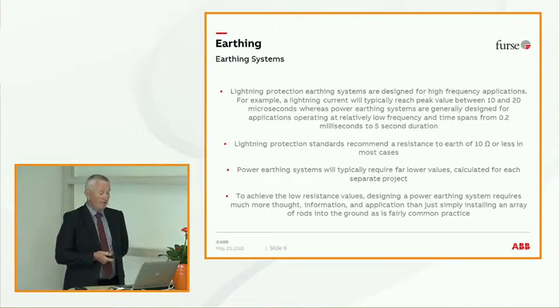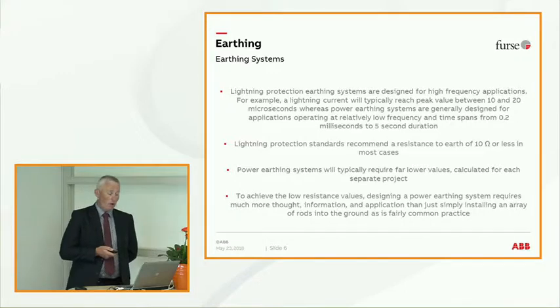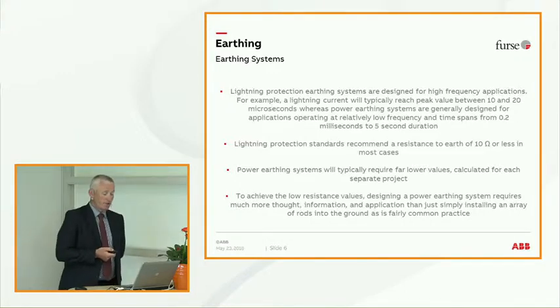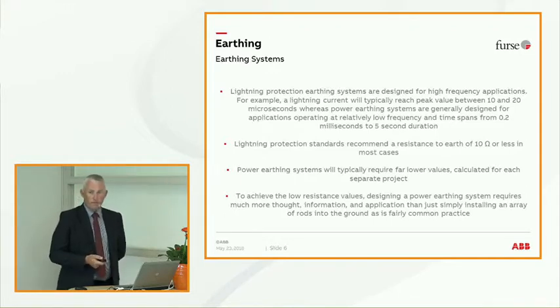Power earthing systems typically have far lower resistance values, in ohms, because we're looking at longer durations and bigger currents. So when you get these power earthing systems, it's generally calculated to the specific requirements. This could be a utility giving you the maximum fault current and the time duration, and then several considerations are taken into account.